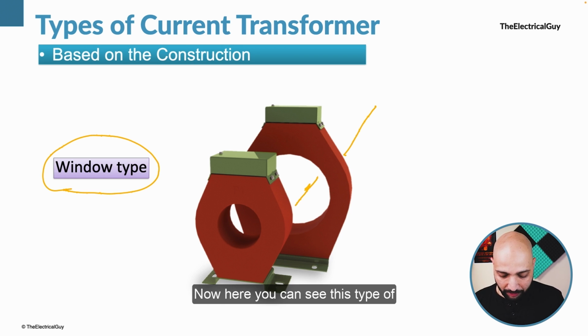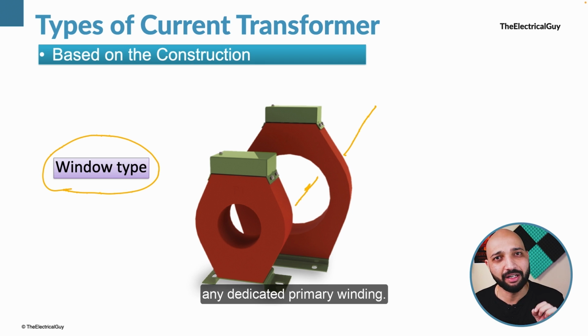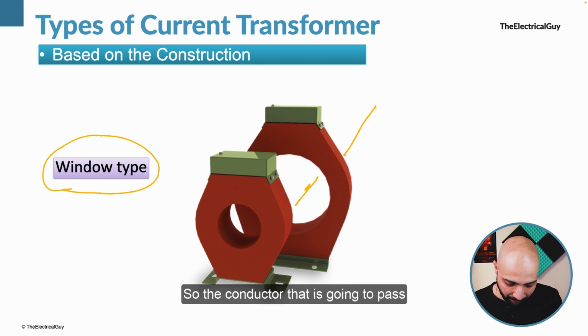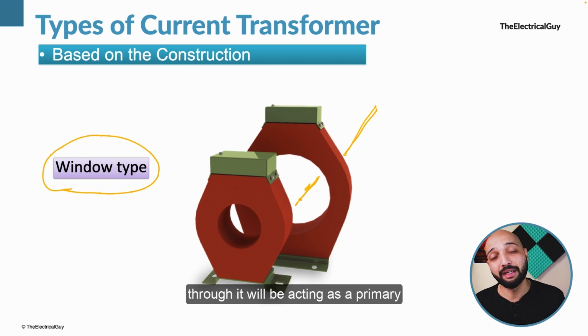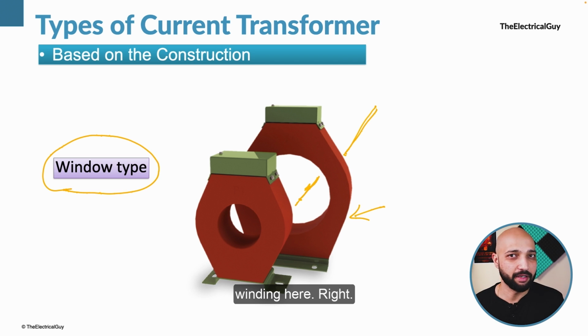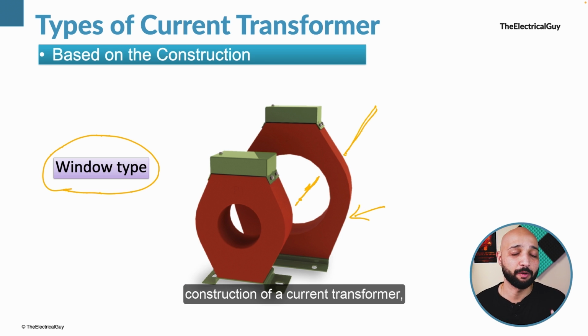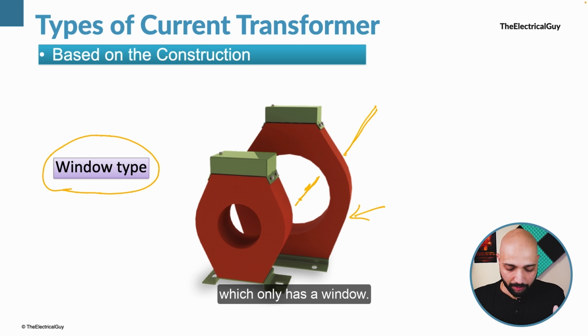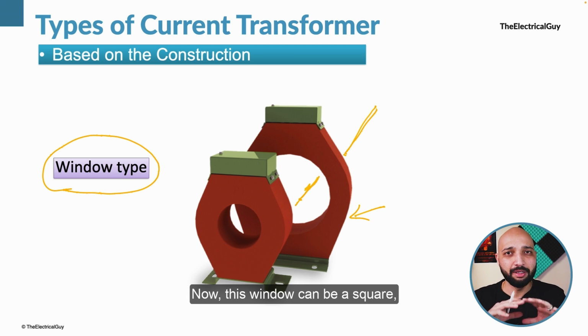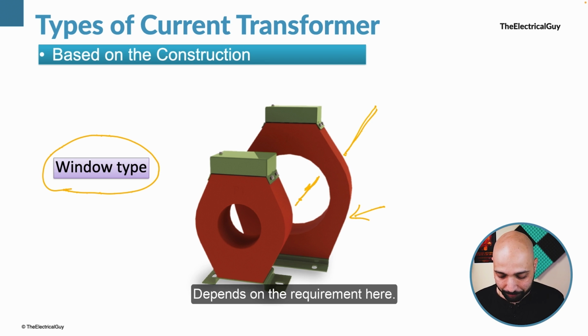Now here you can see this type of current transformer does not have any dedicated primary winding. The conductor that is going to pass through it will be acting as the primary conductor or the primary winding. It will only have the secondary winding here, right? This is the simplest type of construction of a current transformer, which only has a window. Now this window can be a square, an oval, or a circle, depending on the requirement here.